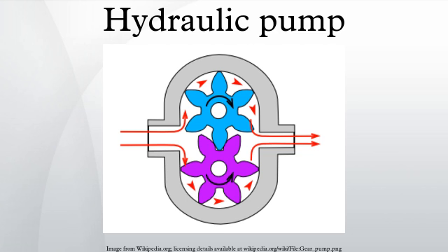These pumps create pressure through the meshing of the gear teeth, which forces fluid around the gears to pressurize the outlet side. For lubrication, the gear pump uses a small amount of oil from the pressurized side of the gears, leads this through the hydrodynamic bearings, and vents the same oil either to the low-pressure side of the gears, or through a dedicated drain port on the pump housing.